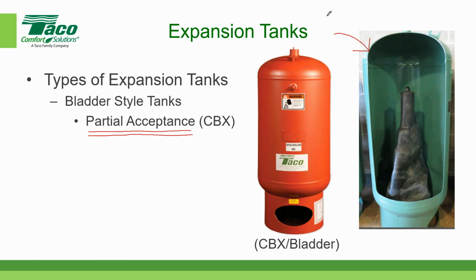That's a partial acceptance, meaning the bladder volume is now a percentage of the steel volume. Using our reference number of 200 gallons for the steel container, I don't know the exact volume of this particular tank, but let's assume the bladder can only hold 50 gallons of water. Since the bladder volume is less than the tank volume, that's called a partial acceptance. So whenever you see the term partial acceptance, it means the bladder only holds a portion of the volume that the steel container has.